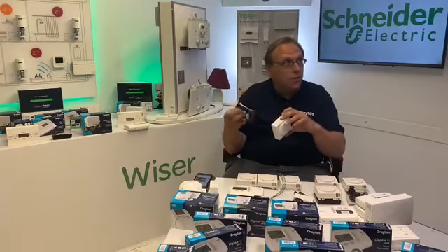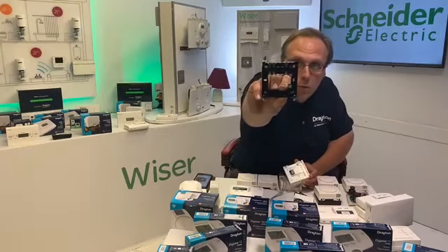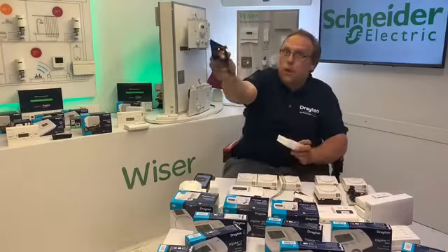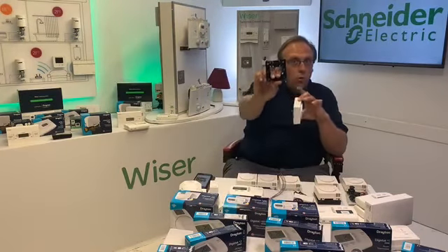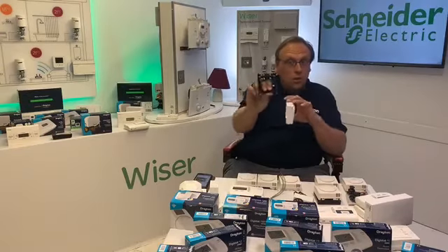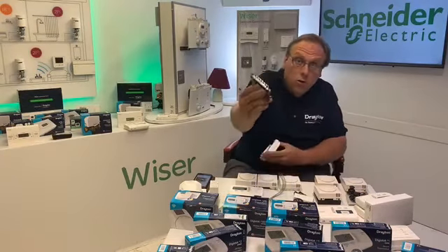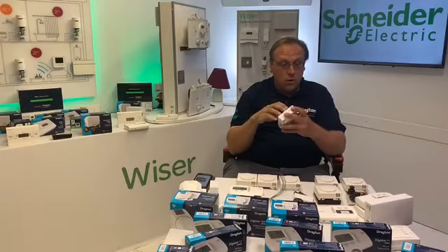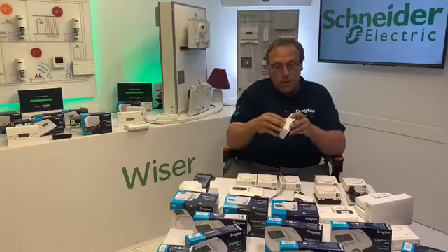It's on, again, the industry standard backplate, but you'll notice on the backplate you've only got the terminals that are going to be used. So if you mix this up with an LP backplate, just make sure that you do get the right backplate for the stat. It will fit, but obviously if you used this on an LP, you are missing some terminals. So just make sure that the backplate that comes with it is the one that you use. But it's a mains powered room thermostat.